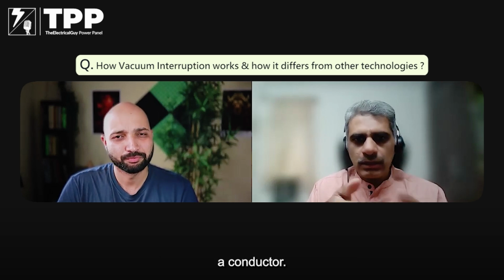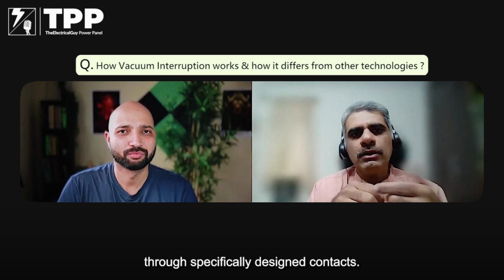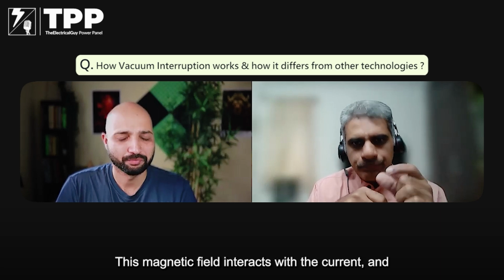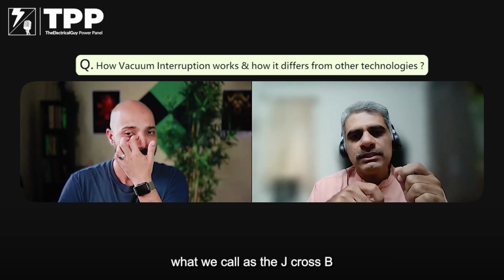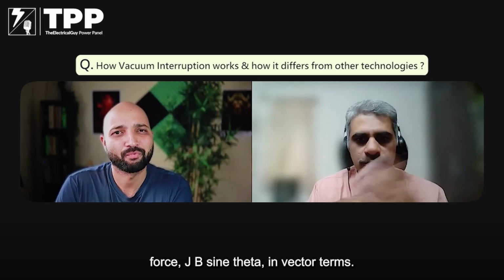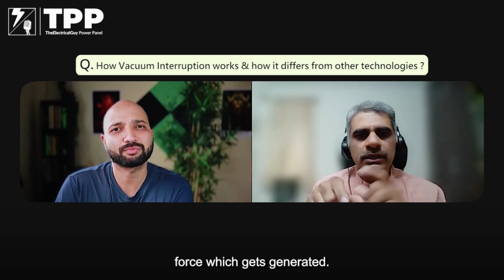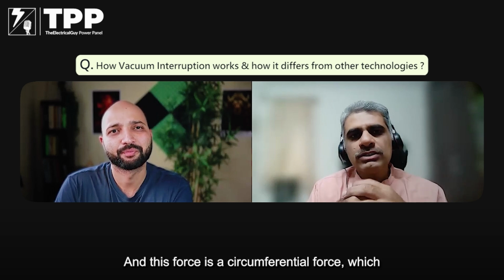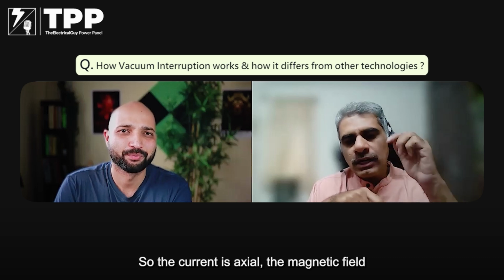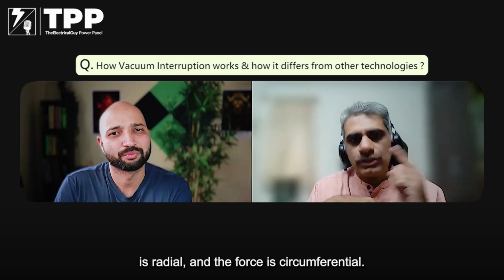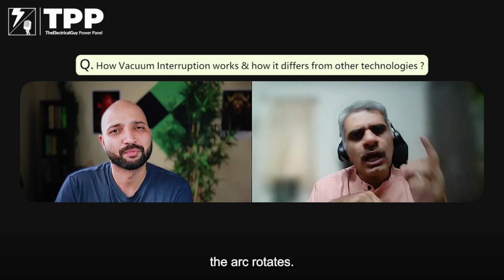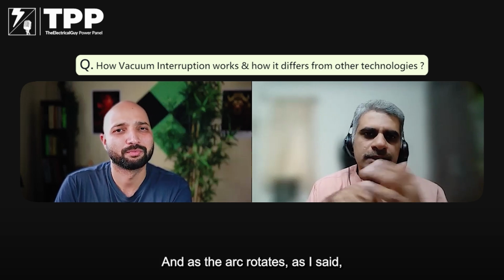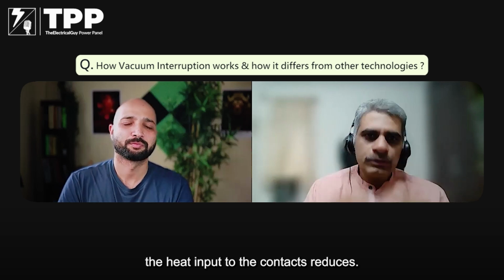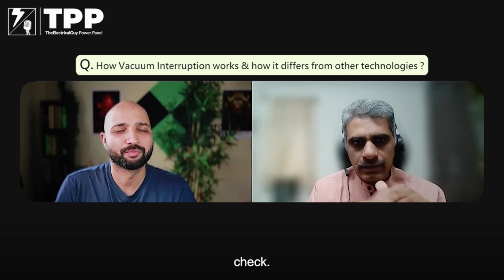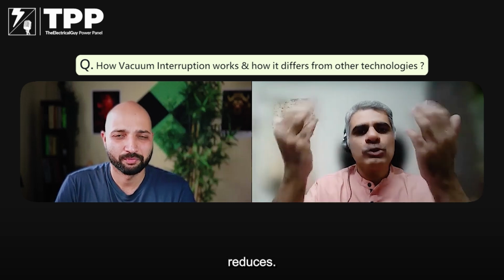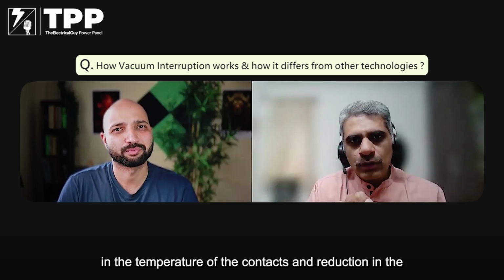The arc is carrying the current, so it's a conductor, and the current itself creates the magnetic field through specifically designed contacts. This magnetic field interacts with the current, and what we call the J cross B force, JB sine theta in vector terms, is the force which gets generated, and this force is a circumferential force which makes the arc rotate. So the current is axial, the magnetic field is radial, and the force is circumferential. Under the influence of the circumferential force, the arc rotates, and as the arc rotates, as I said, the heat input to the contacts reduces. This ensures that the temperature is kept in check, and the generation of the metal vapor also reduces. So the two conditions which are required: reduction in the temperature of the contacts and reduction in the metal vapor.